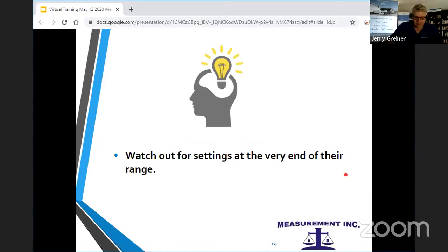So what did we learn from this? You need to watch out for settings that are at the very end of their range. When it says 0 to 8% and it's at 8%, it might be at 8%, but it might really be at 10%, as this was. And when you're working on a setting that's on the end of the range, you really don't know if you're at the end of the range or off the range, as in this case, off the range. So watch out for that.